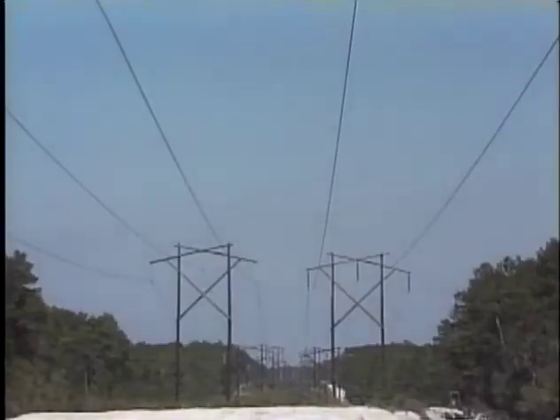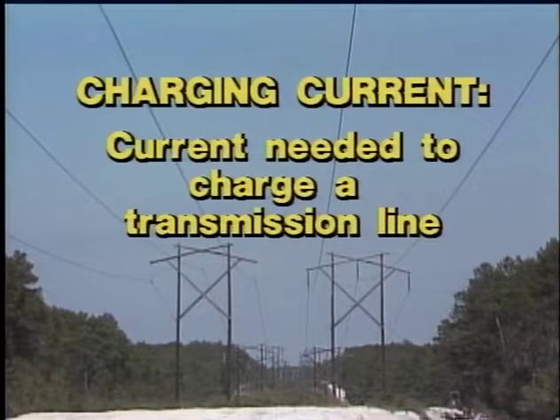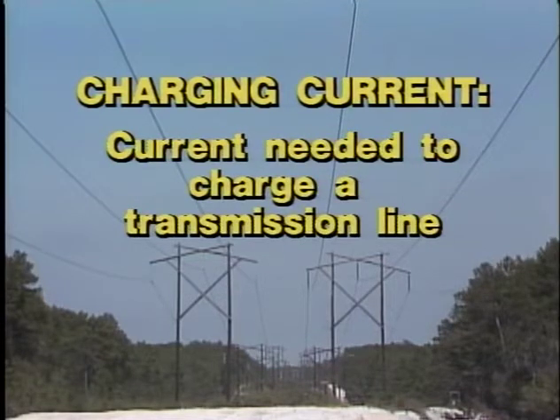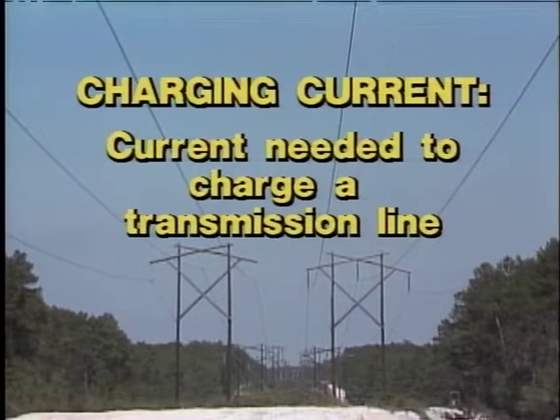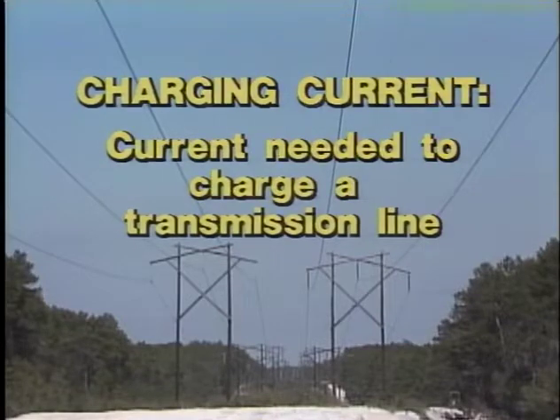Transmission lines also need a certain amount of current that does not perform useful work. The current needed to charge the lines, called charging current, does not perform work. Long, high-voltage transmission lines may draw a lot of non-working charging current in order to deliver working power from one location to another.